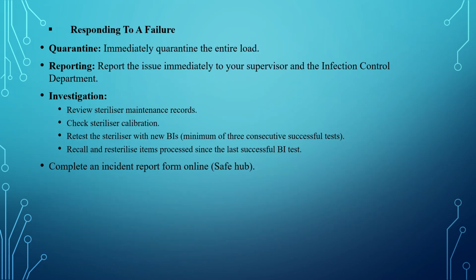Responding to a failure, make sure you quarantine the entire load immediately, before the load has been processed further. Report the issue immediately to the supervisor or infection control department and to the superior. Make sure you investigate, starting from the maintenance record. Check sterilizer calibration. Retest the BI, a minimum of 3 consecutive successful tests. If it passes, then we can use the sterilizer. If it's not, then we need to investigate as well. Complete an incident report form online, which is Safe Hub.